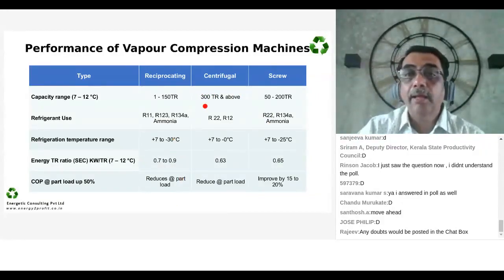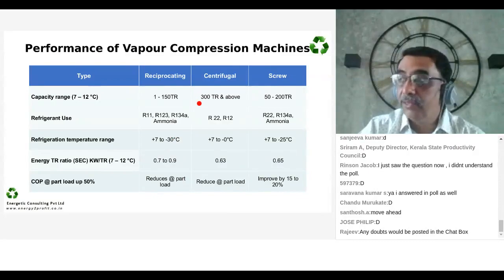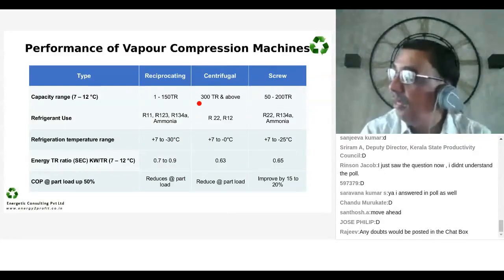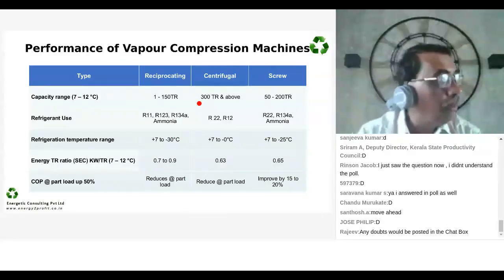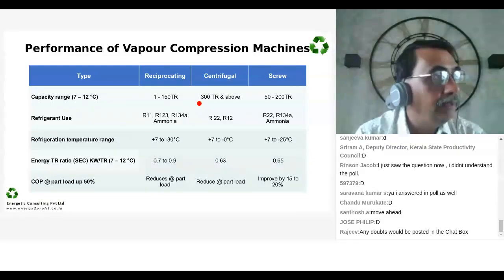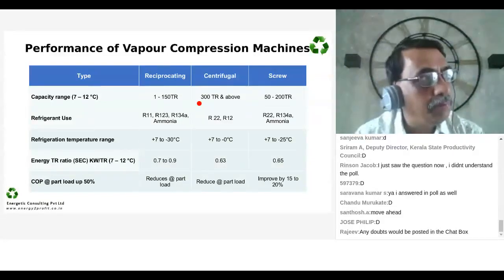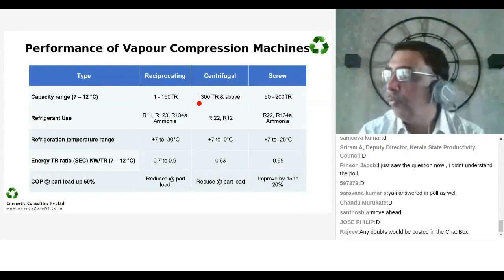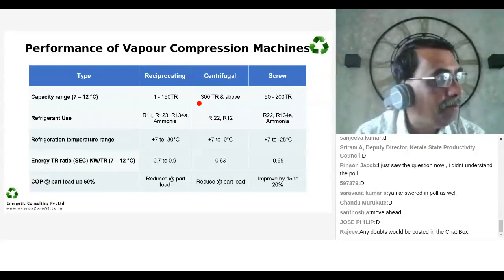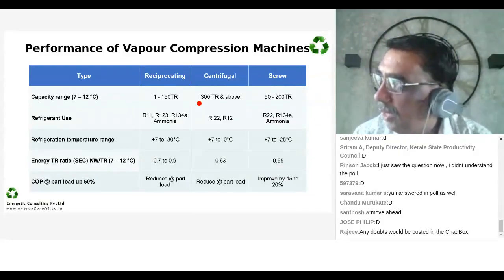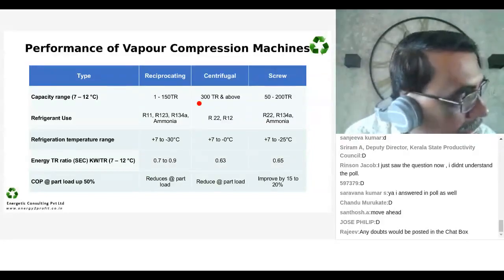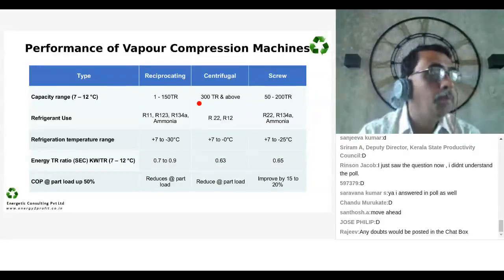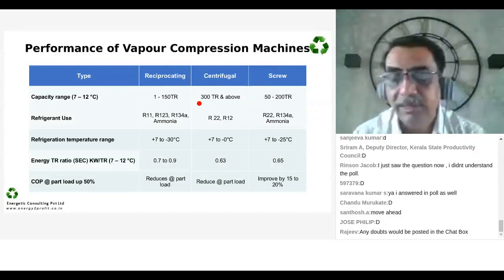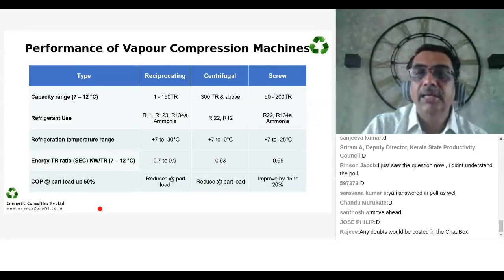And believe me, I have seen a 90 TR machine of Blue Star. I can mention that. We did a measurement. It was operating at 0.5 kilowatt per TR, the Turbocor machine, at various loading from 50% to 100%. Very effective machine, and I'm sure similar machines are available from Voltas and Carrier and other manufacturers. So this is not something proprietary of Blue Star. This is what we measured, so I'm mentioning the name.